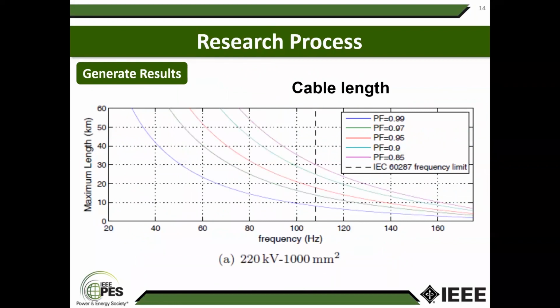Here is the cable length. If your wind farm operates at a power factor of 0.99, at 100 hertz the maximum length achievable is 10 kilometers. But at a power factor of 0.85, you can go up to 40 kilometers. So depending on the length, you can decide what frequency range is available.